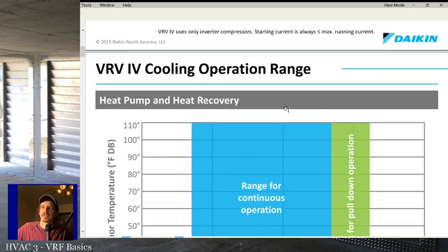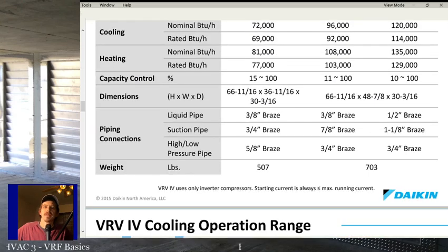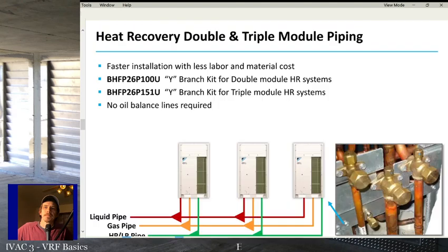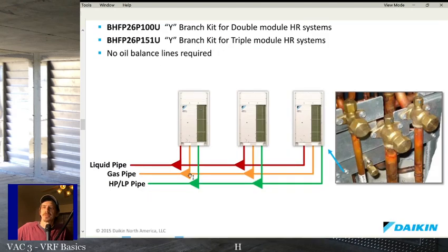Mini splits, for instance, so there's your 3 pipes on that. 3 pipes, outdoor unit, has 3 pipes coming out of it. Smallest line is the liquid line. The biggest line is your suction line. The medium sized line is high pressure, low pressure line.